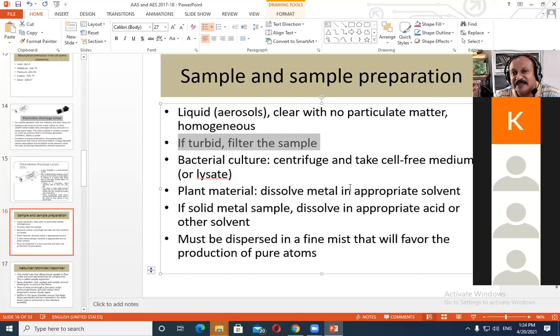It will always be a lesser amount which will be detected by the detector, because something is clogging the capillary, and therefore the sample is not going through the nebulizer into the flame very efficiently. Results will be affected, and after some time it may so happen that the capillary will be completely blocked, and nothing from your liquid sample will go into the flame, and therefore your analysis will not be done properly.